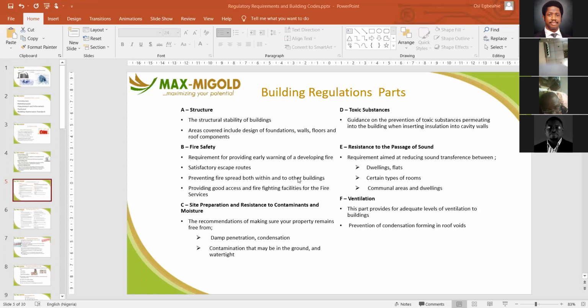Part of the problem, especially with suspended ceilings in buildings, is that the wetness you see on the ceiling is sometimes not due to any leakage but to thermal change. If the air conditioning is working well and there's no way for it to properly vent out, by the time there's a change in temperature in that room, condensation begins to show on the ceiling. The ceiling begins to sweat, then dampens and changes color, and you think there's a leak. But there's no leak, just no proper venting or air exchange in that space. That's why it happens, so you must always ensure proper ventilation for your roof.